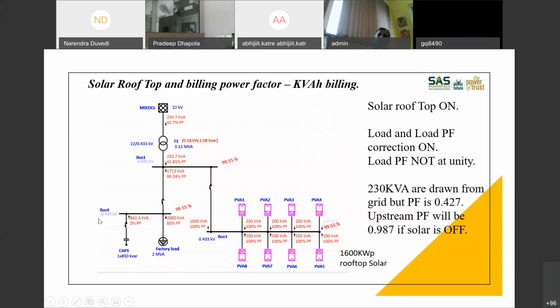If you compensate it totally locally, then nothing will happen at whatever power you operate your solar plant with. If it is more, it will go back to grid. If it is less, your plant will consume it, and no change will happen at this place. But if your local power factor is not compensated correctly, then it can definitely affect this, because load requires active as well as reactive power.